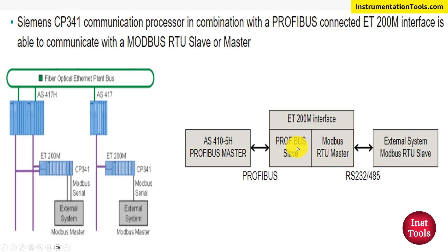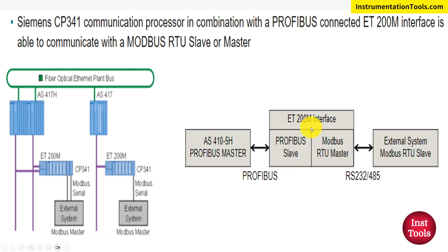The data is converted into Profibus data packets. As we already know, Profibus communicates with master and slave. The ET200M acts as a slave device and the Automation Station or PLC acts as the master device. A protocol conversion is happening at the ET200M level. How the data transfers and how the request happens will be discussed in the next slide.